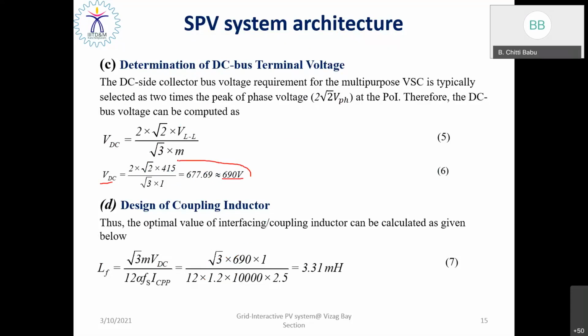in order to have an inverter output voltage of 415 volts line to line, where M is the modulation index for the inverter. And the design of the coupling inductor: the coupling inductor has been incorporated in the inverter output to filter out the current ripple present in the inverter current. So as the DC link voltage is 690 volts and the switching frequency of the inverter is about 10 kilohertz, we would be able to design the filtering inductor at about 3.31 millihenry per phase. It is very essential to filter out the current ripple present in the inverter switches.